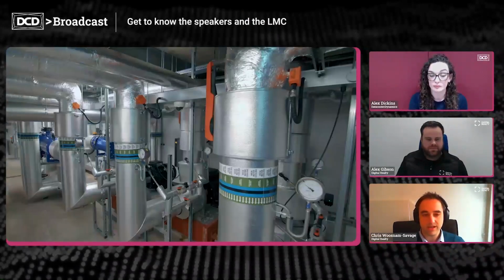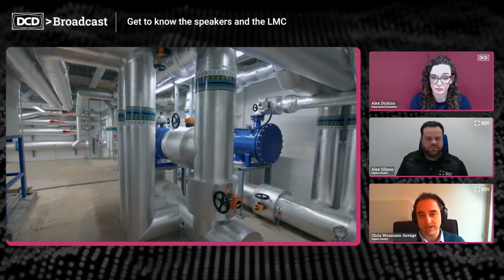What does make Cloud House a little bit unique is its approach to cooling. So it uses the dock water that is adjacent to the building and passes it through a set of heat exchangers. This then cools the water loop within the building that then serves the CRAs, and finally the raised access floor delivers the cold air to the cabinets. So it provides a very energy efficient cooling system, and there's also the benefit that during that process, there's no water lost.